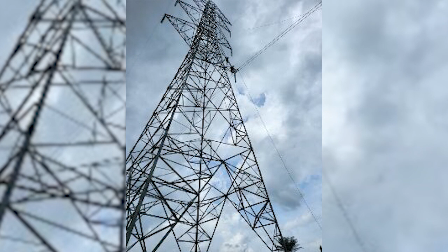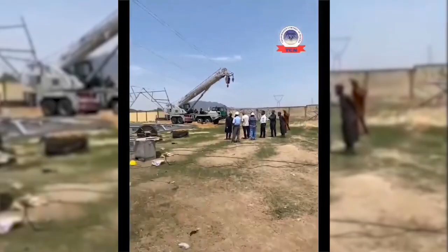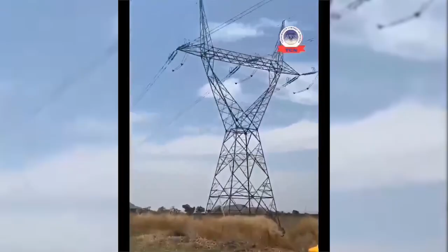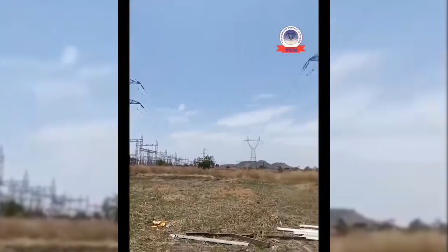TCN is also constructing a new transmission tower to enhance the resilience and flexibility of the network. This will allow the Bauchi and Gombe transmission substations to act as mutual backups in the event of maintenance or a fault. With this switch point, the Jos transmission substation could supply Bauchi substation directly through a 132 kV transmission line, whenever the primary 330 kV connection from Gombe is unavailable. This new arrangement enhances power reliability, diversifies transmission routes, and improves emergency response efficiency.